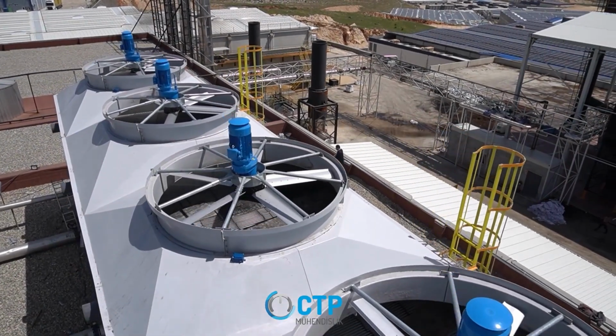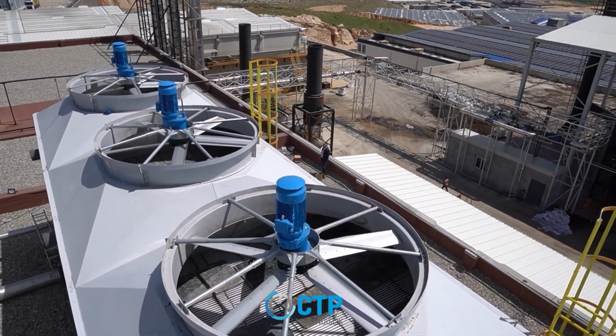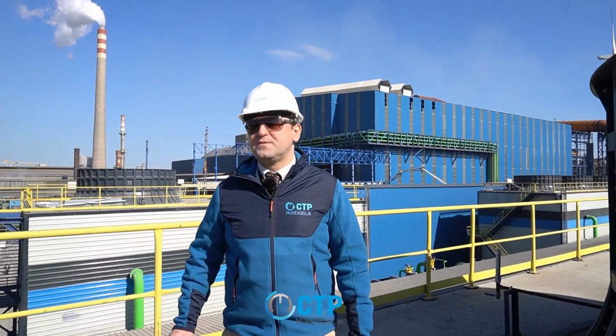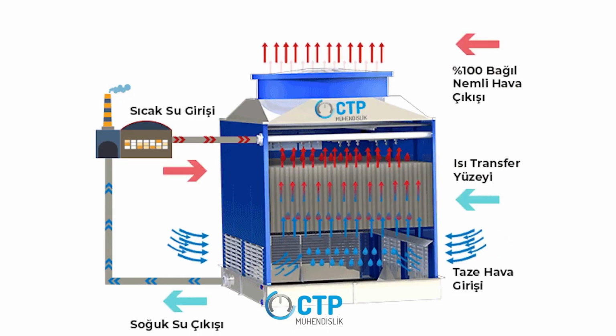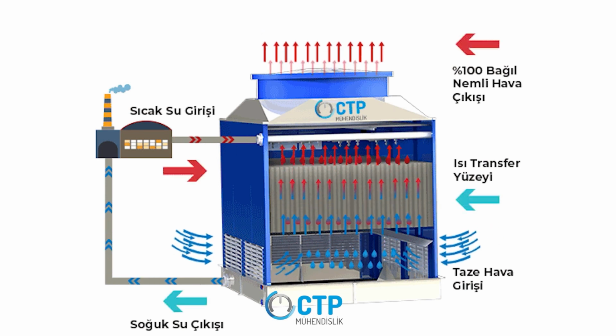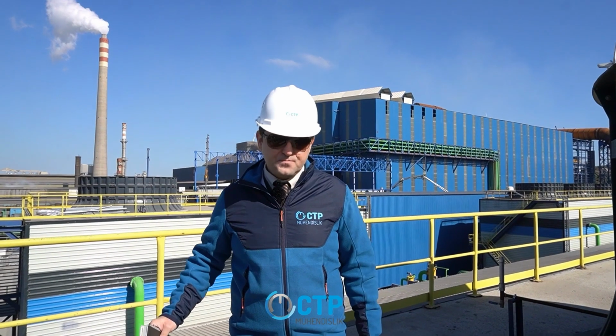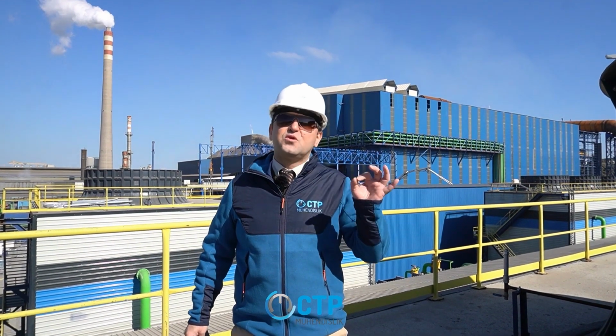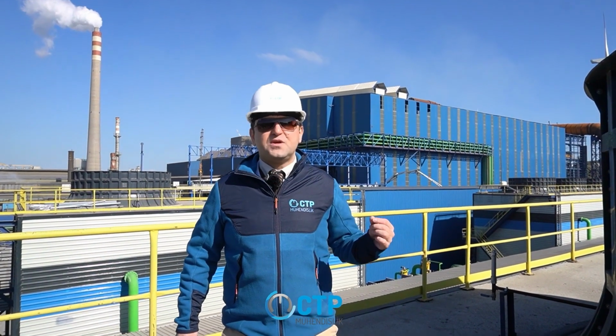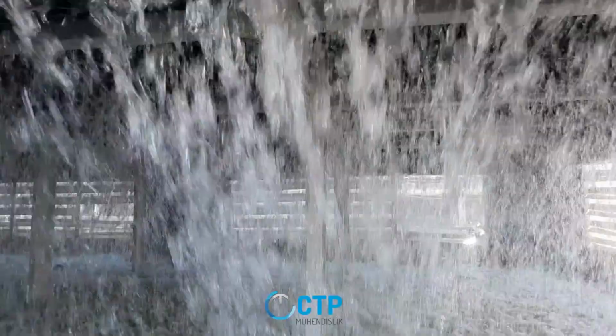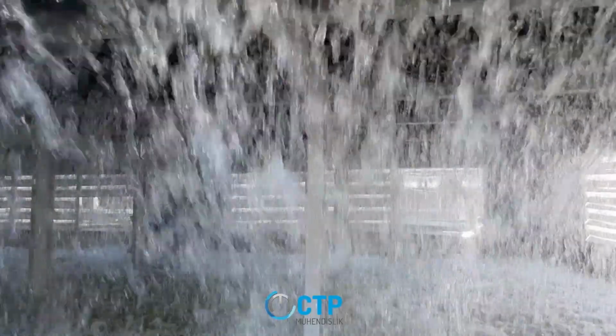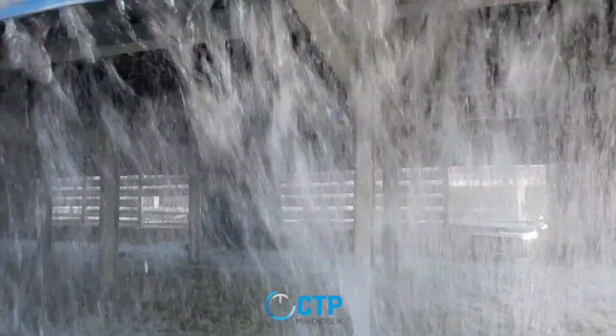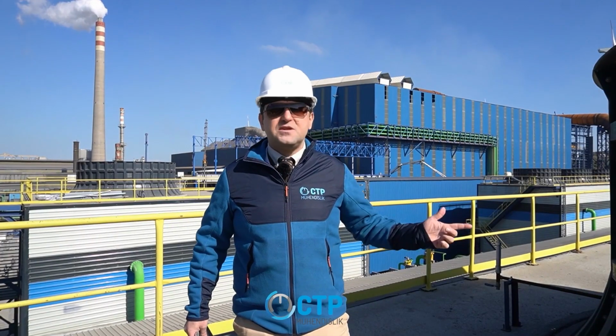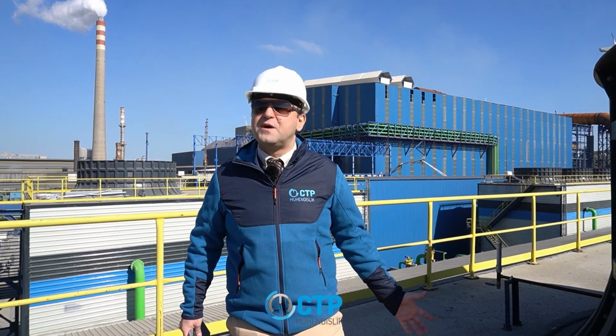The water you supply to the tower decreases somewhat and returns to the pool due to evaporation. After that, it is sent back by pumps to whatever process, machine or equipment is being used there. While doing this, of course, as I mentioned at the beginning, we break the water into very small droplets. Because there is a forced airflow inside, some of those very small droplets can be carried upward without falling down. Fortunately, a droplet separator system is in place that prevents this from happening.